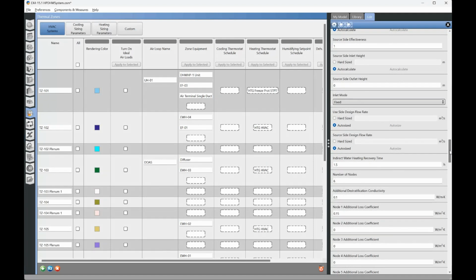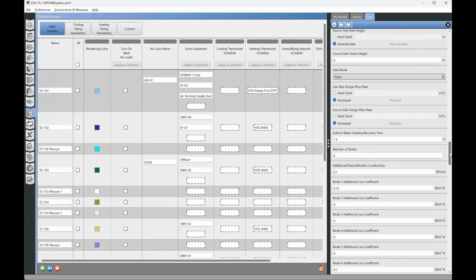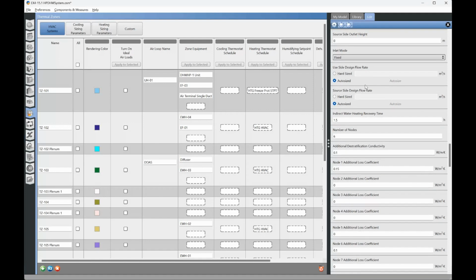Design flow rates, use side and source side. Those are going to be auto-sized. Some nomenclature about this: the use side of the tank is basically considered the connections for going out to the systems, because the system is going to be using that hot water. In general, it draws hotter temperatures from the tank and returns colder temperatures to the tank. Whereas source side connections are drawing colder temperatures from the tank and returning hotter temperatures to the tank. So that's the nomenclature there.